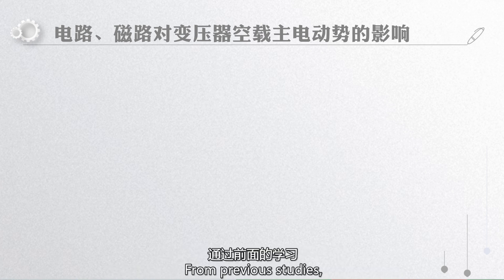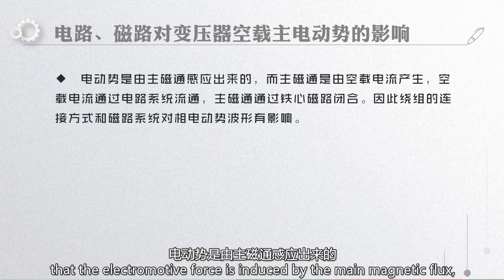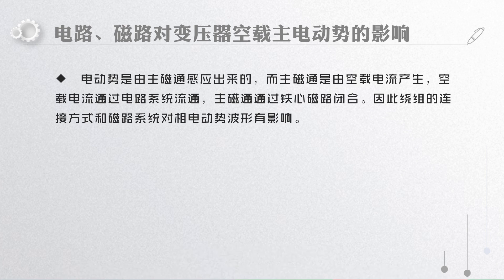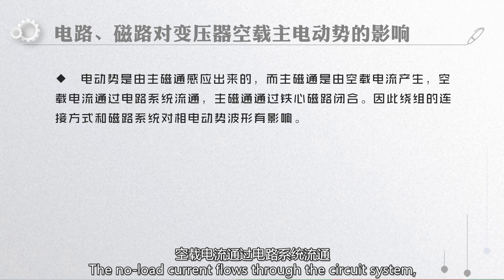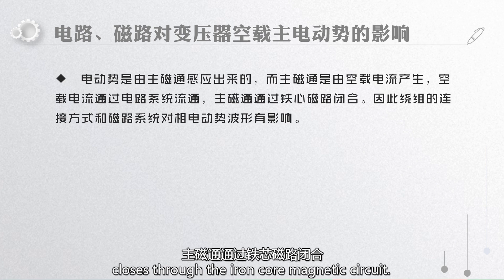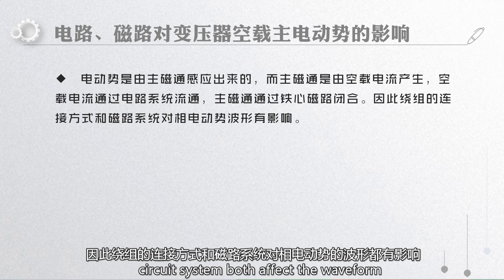From previous studies, we know that the electromotive force is induced by the main magnetic flux, and the main magnetic flux is generated by the no-load current. The no-load current flows through the circuit system and the main magnetic flux closes through the iron core magnetic circuit. Therefore, the connection method of the winding and the magnetic circuit system both affect the waveform of the phase electromotive force.